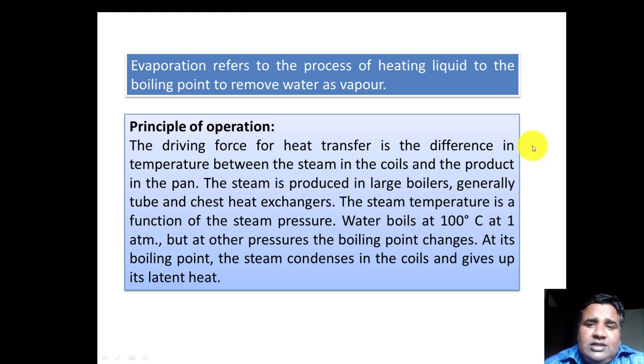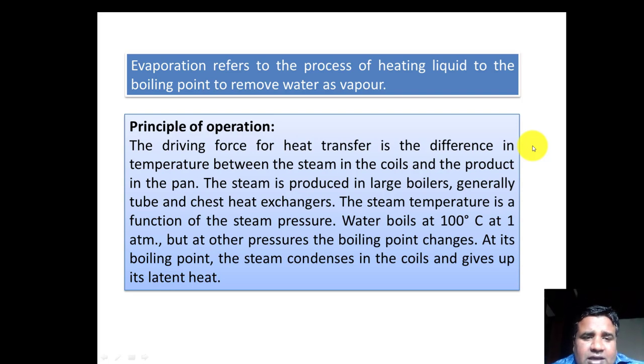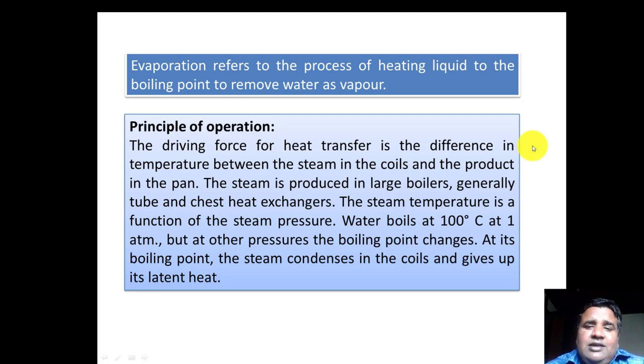The steam is produced in large boilers, generally tube and chest heat exchangers. The steam temperature is a function of steam pressure — if we increase the pressure then we can maintain high temperatures. Water boils at 100 degrees centigrade at one atmospheric pressure but at other pressures the boiling point changes. At its boiling point, the steam condenses in the coils and gives up its latent heat, transferring it to the product inside, and it condensates.